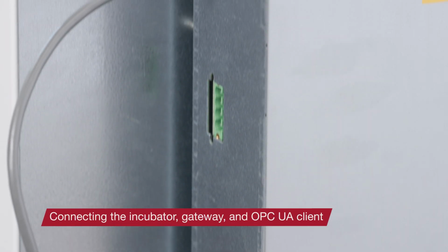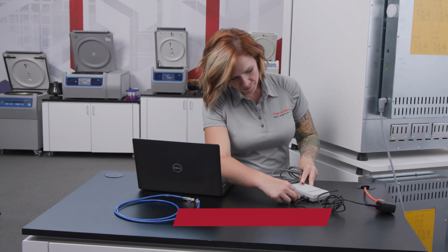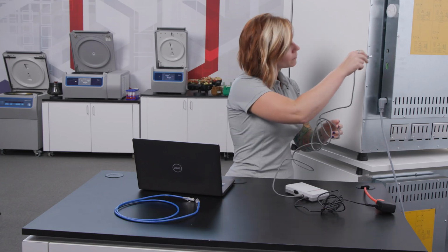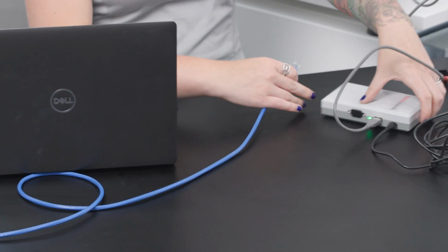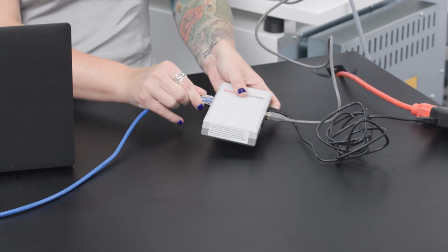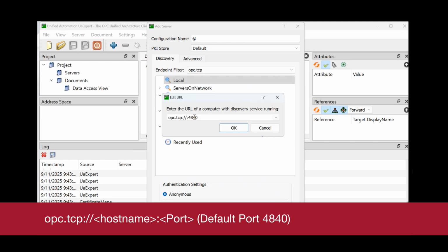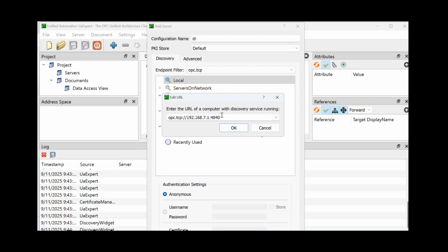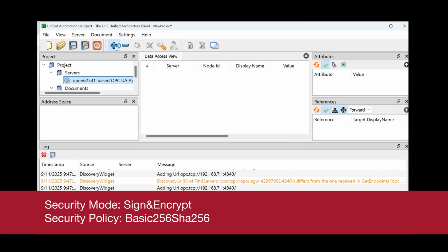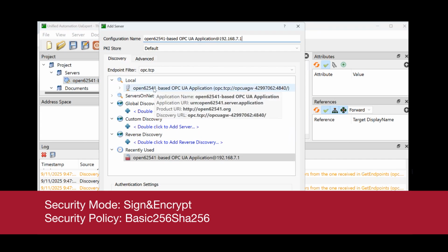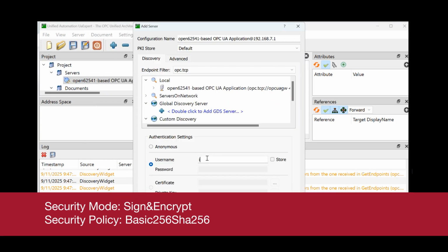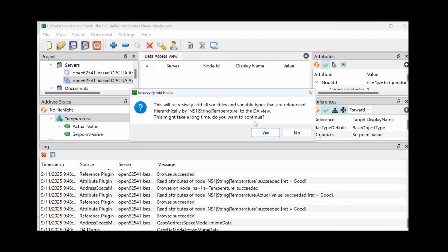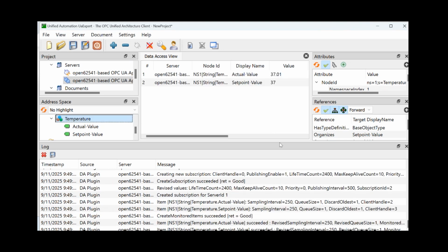Now you're ready to connect the incubator, gateway, and the OPC UA client. Using a USB cable, connect the incubator to the gateway and use an Ethernet cable to connect the gateway to the OPC UA client. Use the OPC UA client to create an OPC link to the OPC server by entering the server URL shown here. If you don't connect using the hostname, you can create the link using the IP address as part of the same syntax. Once you're connected, the safety certificate shown here is used. Again, you'll need your OPC username and password defined during the configuration. With the OPC link set up, you're able to monitor and share data from the attached Vios iDx CO2 incubator.